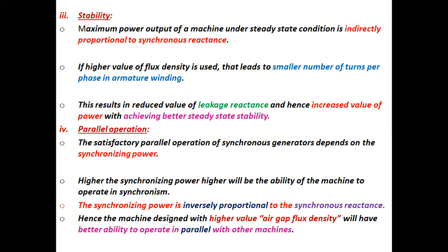Parallel operation. The satisfactory parallel operation of synchronous generators depends on the synchronizing power. Higher the synchronizing power, higher will be the ability of the machine to operate in synchronism. The synchronizing power is inversely proportional to the synchronous reactance. Hence, the machine designed with a higher value of air gap flux density will have better ability to operate in parallel with other machines.